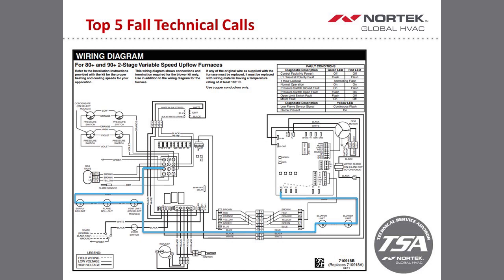The easiest way to jump out this limit circuit for testing is to follow the blue wire out of your 12-pin plug to the first limit it comes to. All you have to do is unplug it from that limit and then take that blue wire back to the R terminal. That will effectively eliminate the limit circuit in the 2-stage equipment.